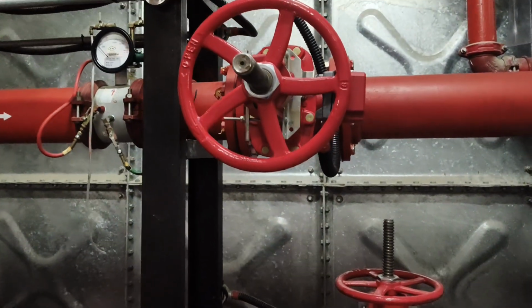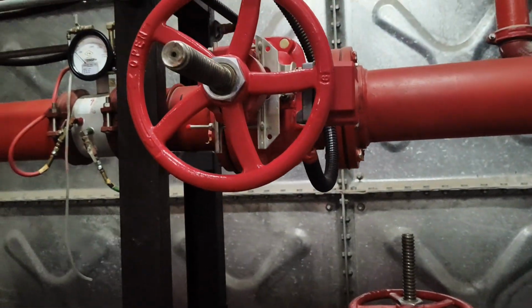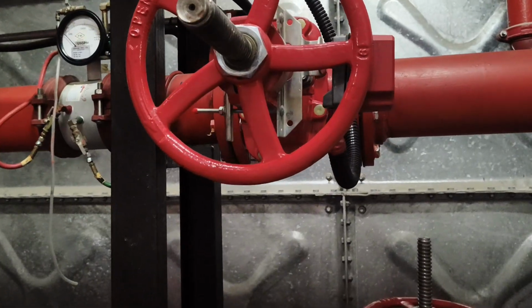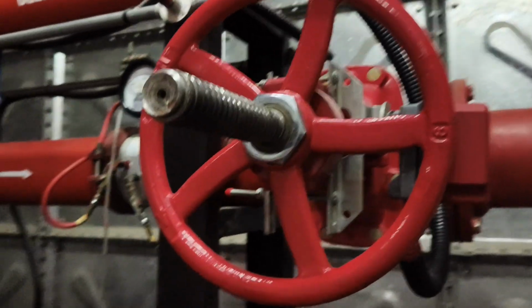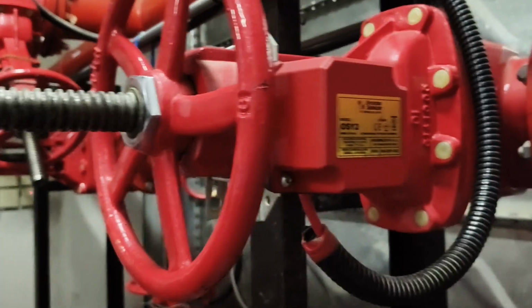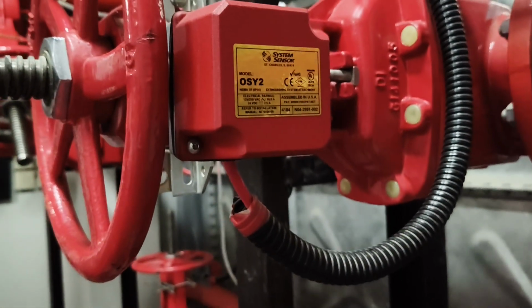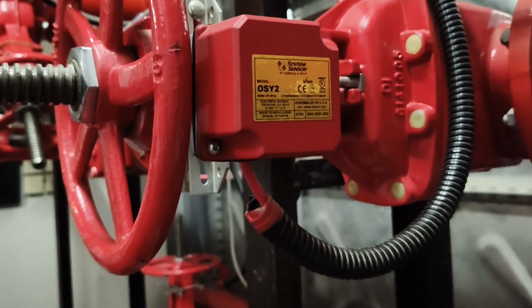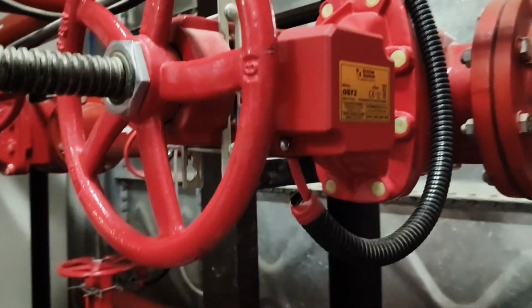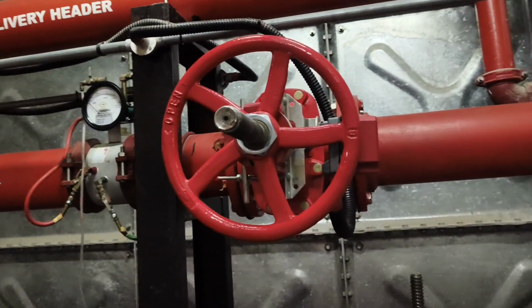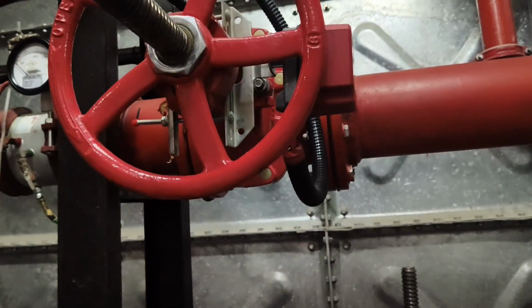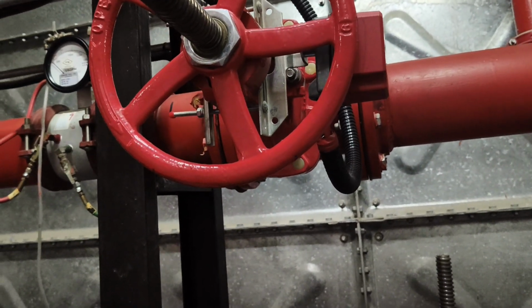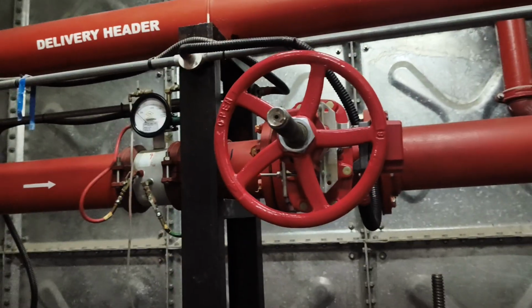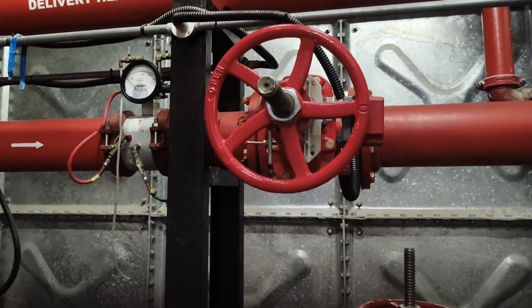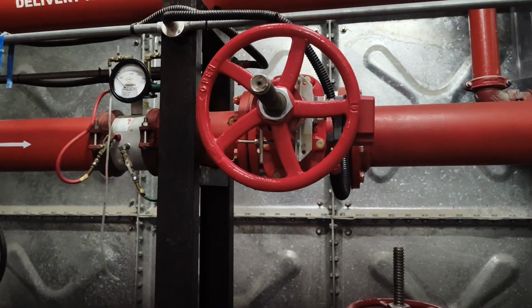Close to the OS and Y valve is what we call the tamper switch, a system sensor tamper switch. What is the work of the tamper switch? Since this is normally open and has been wired and connected, if anybody tampers with it or tries to close it, it will give a signal to the fire alarm panel.